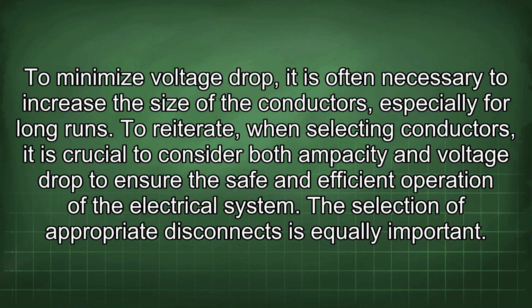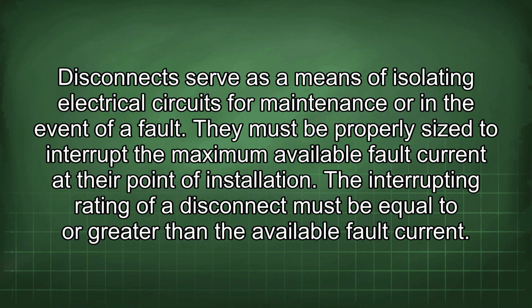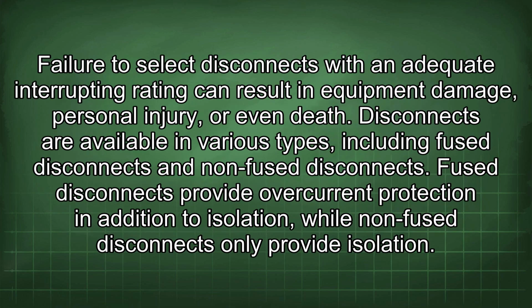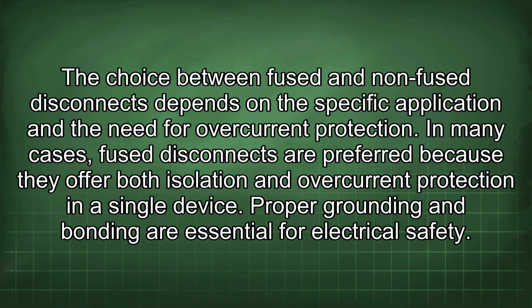The selection of appropriate disconnects is equally important. Disconnects serve as a means of isolating electrical circuits for maintenance or in the event of a fault. They must be properly sized to interrupt the maximum available fault current at their point of installation. The interrupting rating of a disconnect must be equal to or greater than the available fault current. Failure to select disconnects with an adequate interrupting rating can result in equipment damage, personal injury, or even death. Disconnects are available in various types, including fused disconnects and non-fused disconnects. Fused disconnects provide overcurrent protection in addition to isolation, while non-fused disconnects only provide isolation. The choice between fused and non-fused disconnects depends on the specific application and the need for overcurrent protection. In many cases, fused disconnects are preferred because they offer both isolation and overcurrent protection in a single device.